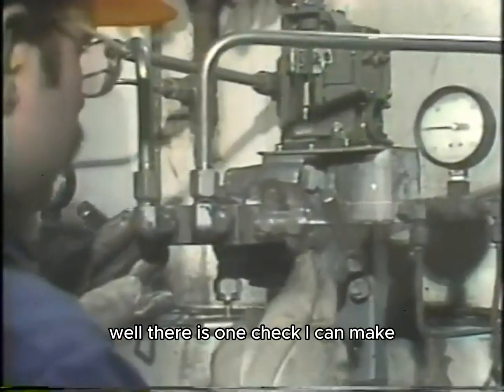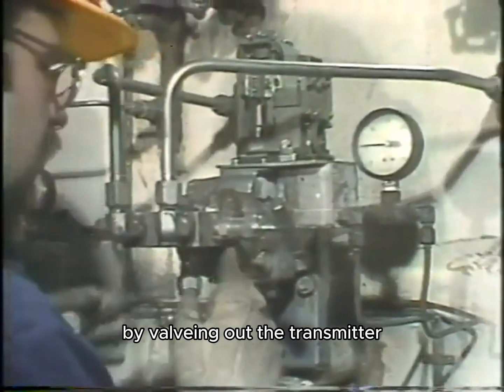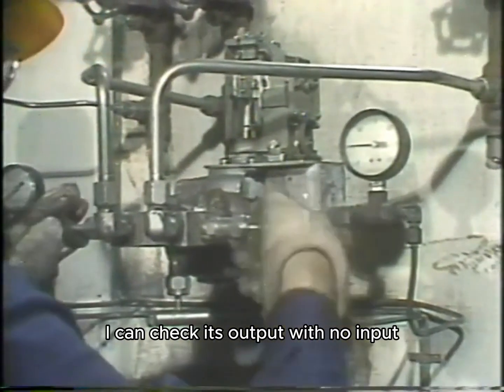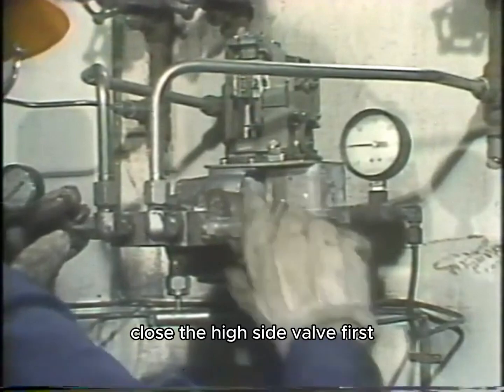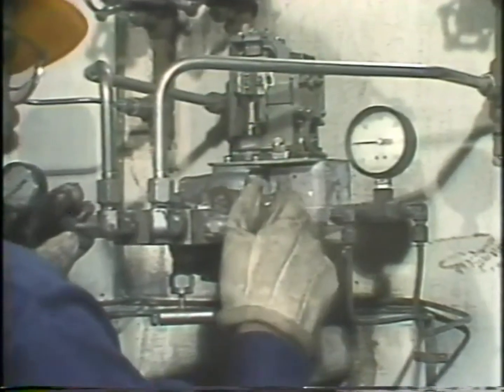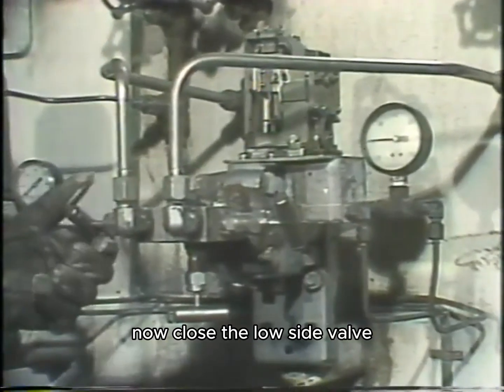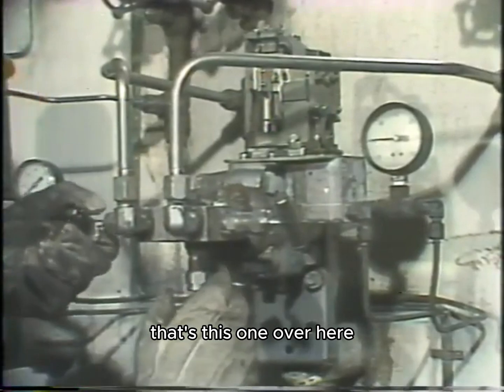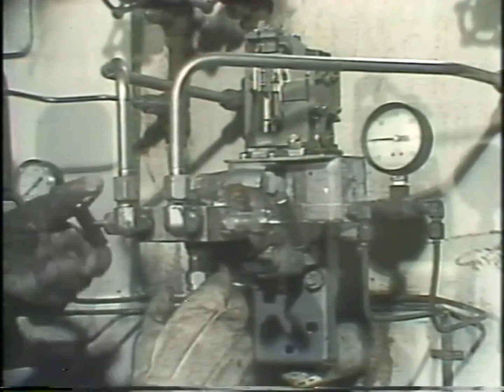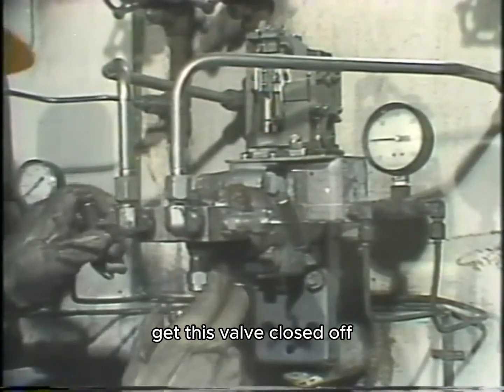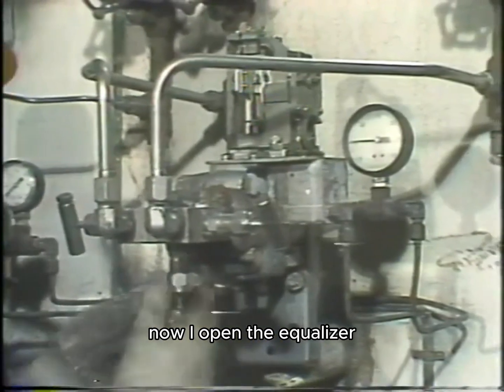Well, there is one check I can make while I'm here in the field. By valving out the transmitter, I can check its output with no input. Close the high side valve first. Now I'll close the low side valve. That's this one over here. Get this valve closed off. Now I open the equalizer.